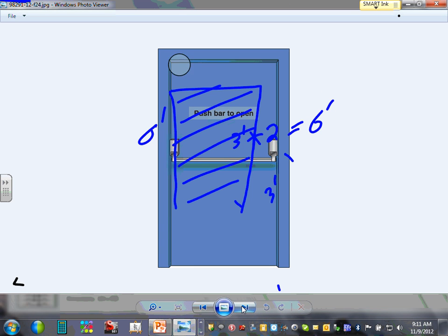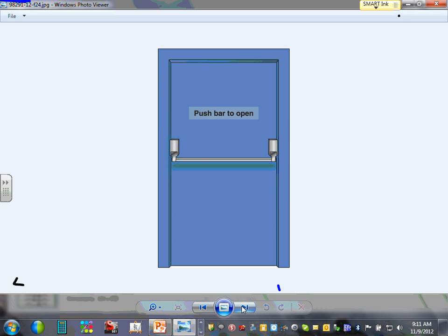The electrical room also requires a door, a panic door like this. So if this is electrical room, guys, for large equipment. Does this door qualify as a door for electrical room? No. Why? Because you have to twist. So it has to look like a panic door like this. Like egress doors, all egress doors in any building require this type. If you look at the hallways, doors in the hallways or stairways, they all require called the egress door. You throw yourself in them and they open.